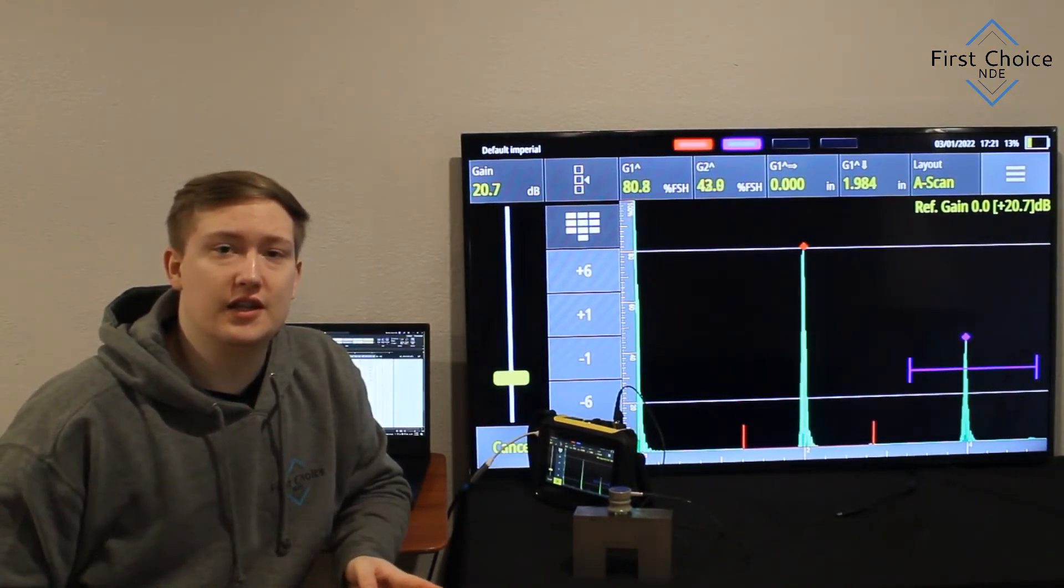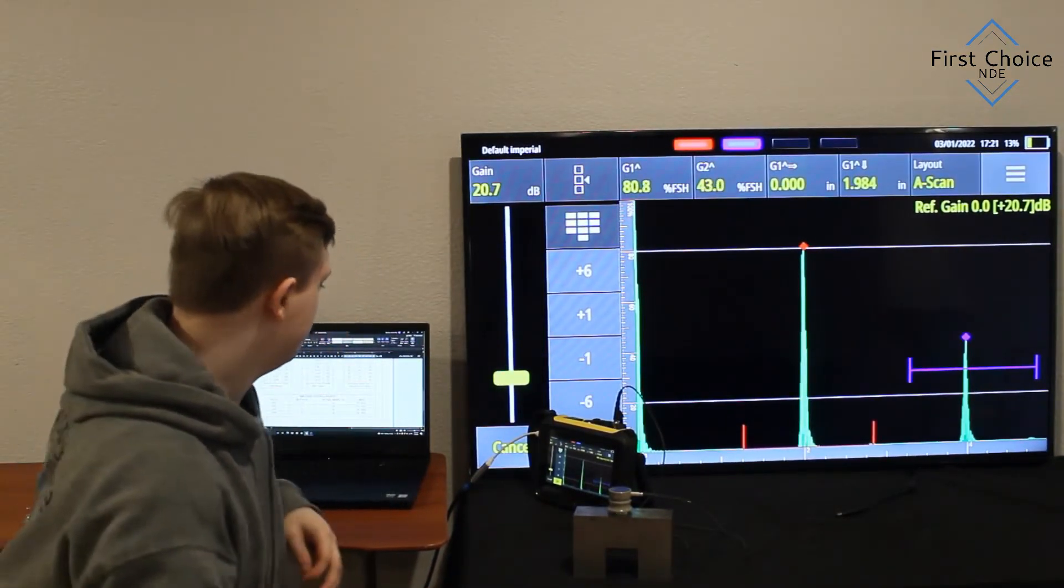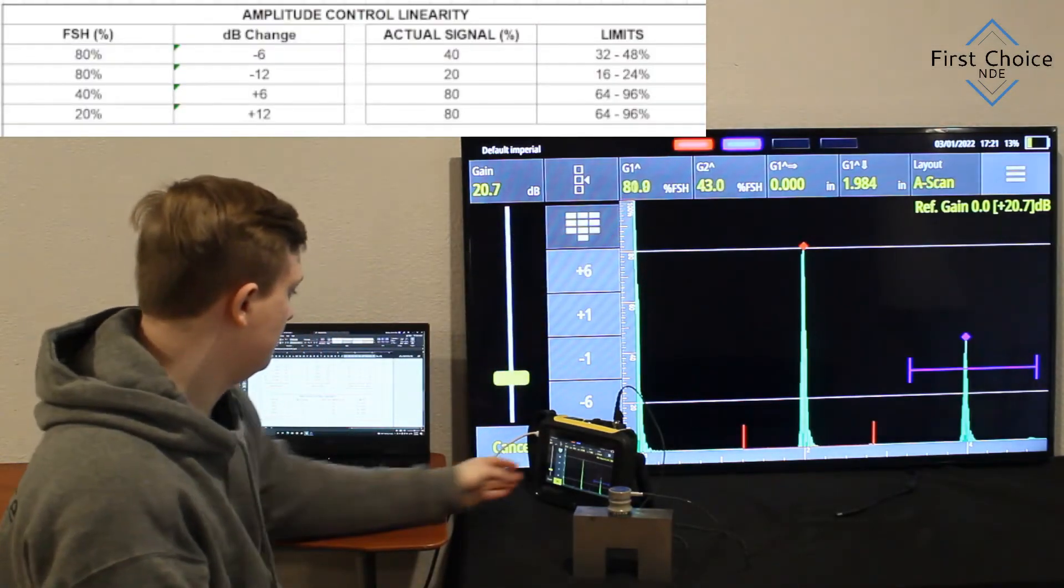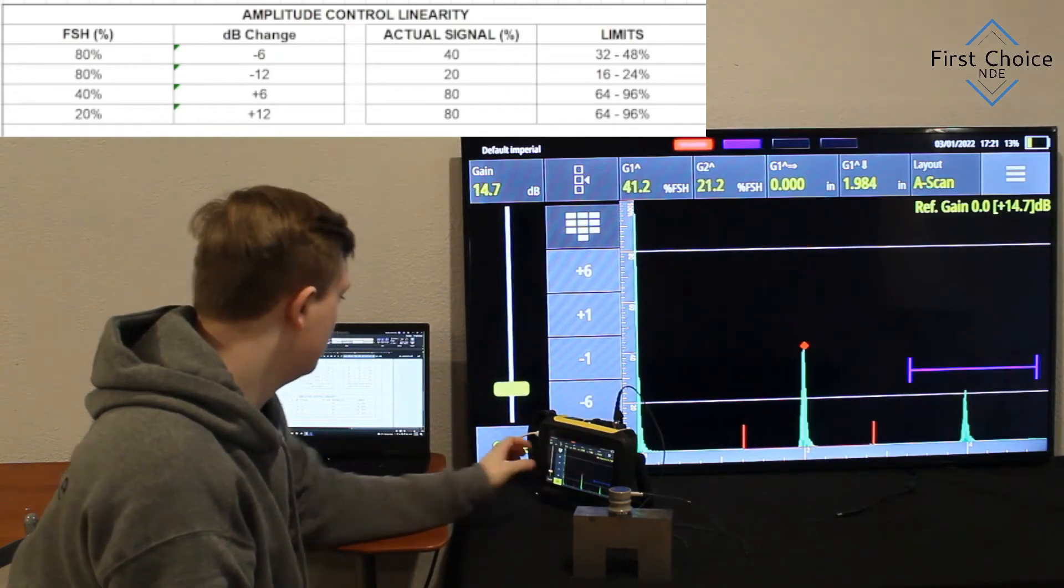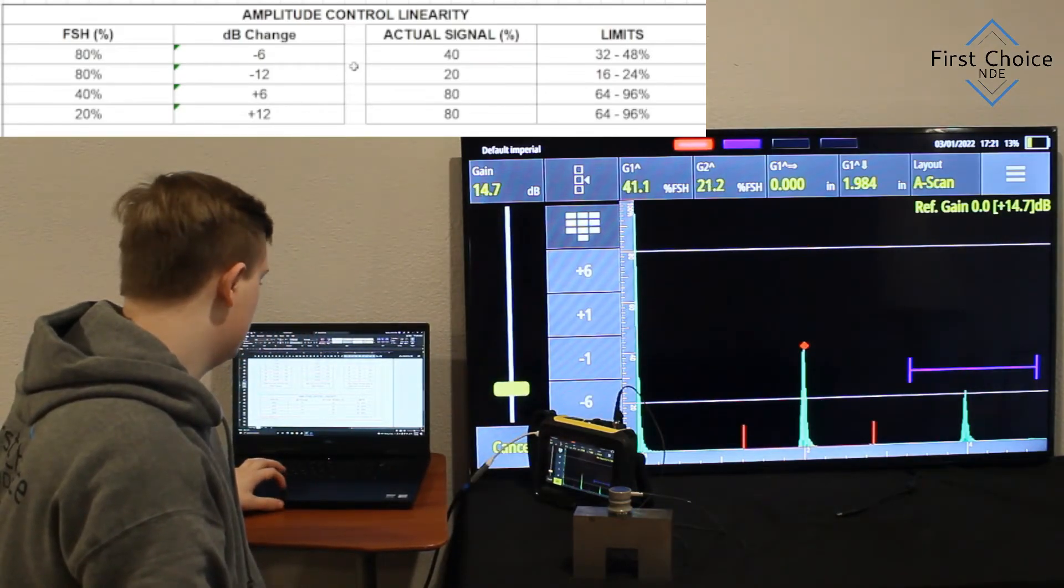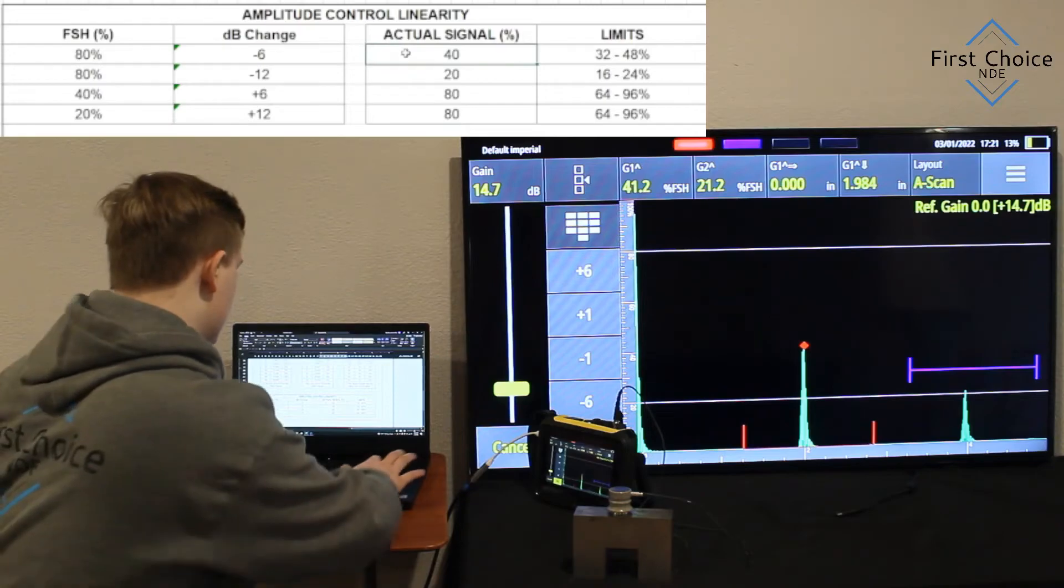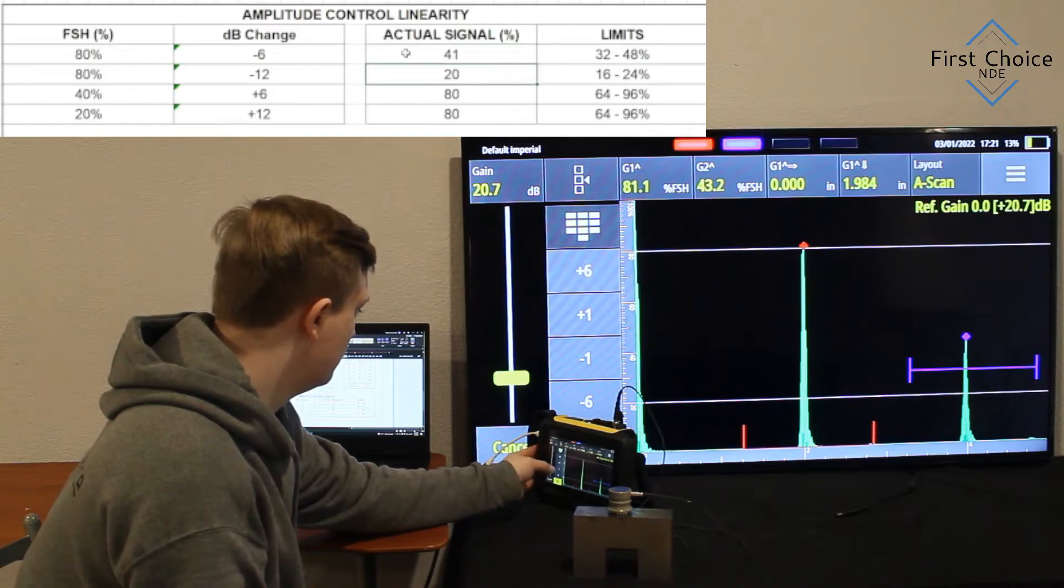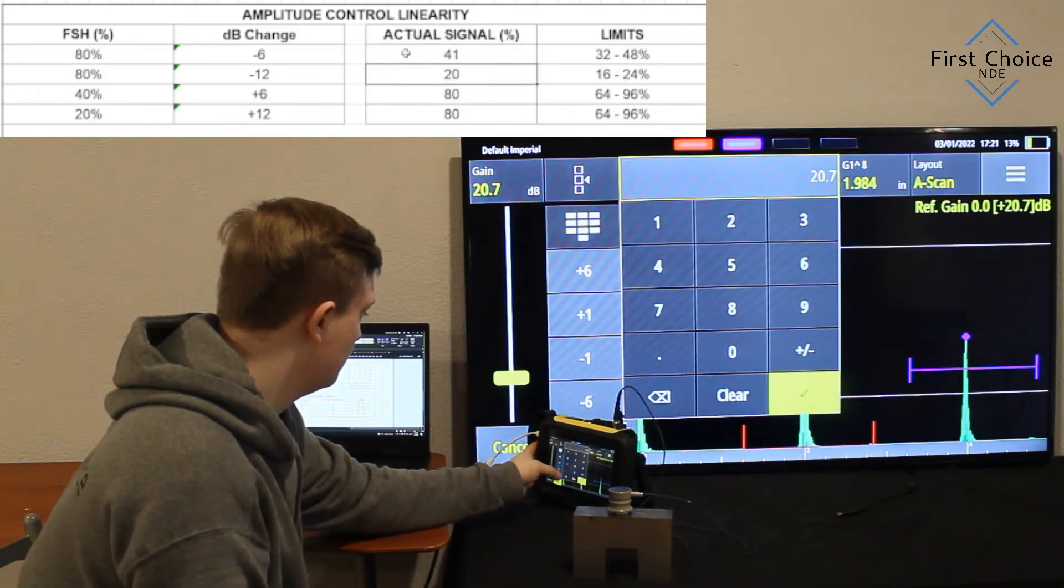And this is the amplitude control linearity. Alright, so what I'm doing right now, on the top left, is the Excel file. That way I'm inputting numbers in. So when you look on the left, you see the signal is at 80%. So what you do is you drop it 6 dB, and that should drop it 50% screen height. And so it should drop it to 40. It was, in our case, 41.